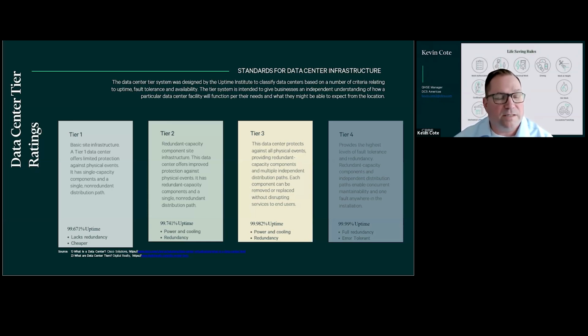For instance, tier 1 is just the basic. You have a full load data center that needs 4 generators to operate, and it only has 4 generators. If one goes down and you need that generator, you won't have enough power. That's your N, or tier 1 type of system, at 99.671% uptime.